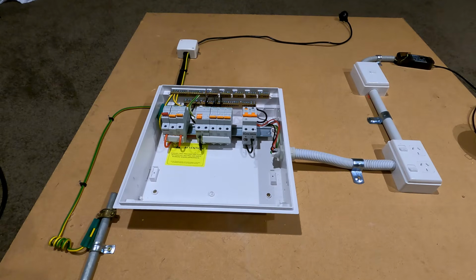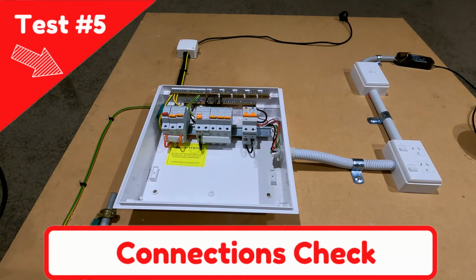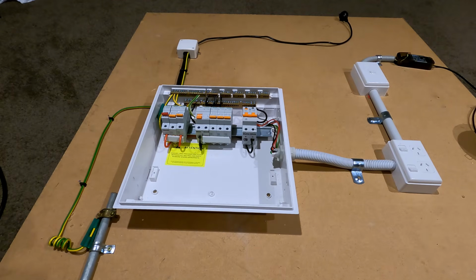Alright, sweet. So the final test before livening the installation is we're going to check the correct circuit connections. The regs want you to verify 3 things. The first one is short circuits. Well, I've already done the Megger test, which rules pretty much all of that out. The next one is transposition. Now we've done our polarity tests, we've ruled that one out. And the last one is interconnection.